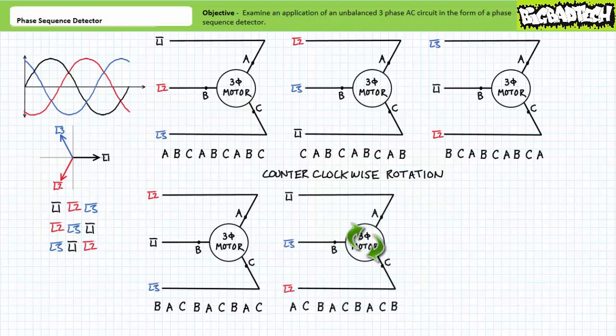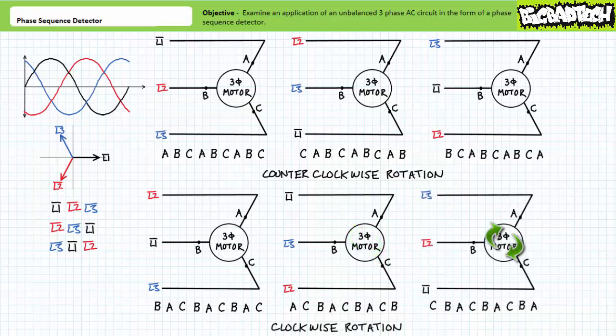You'll find similar clockwise rotational behavior with L1 landed at A, L2 landed at C, and L3 landed at B, where the magnetic poles established by the stator rotate from A to C to B and back again, ACB, ACB, establishing clockwise rotation. Similarly, with L1 landed at C, L2 landed at B, and L3 landed at A, the magnetic poles rotate from C to B to A and back again, CBA, CBA, establishing clockwise rotation.